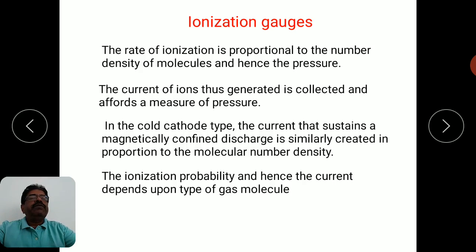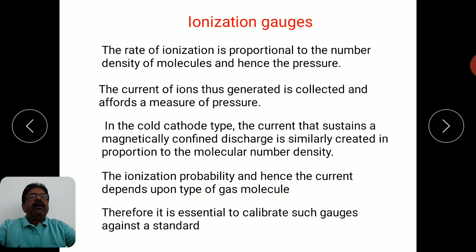So it is different for different gas molecules, and therefore it is essential to calibrate such gauges against a standard one. It is quite difficult to calibrate such ionization gauges because they are dependent upon the gas species. So you should calibrate them with the help of some standard.